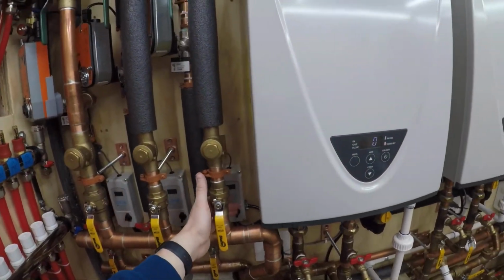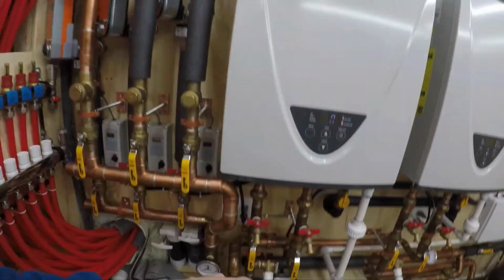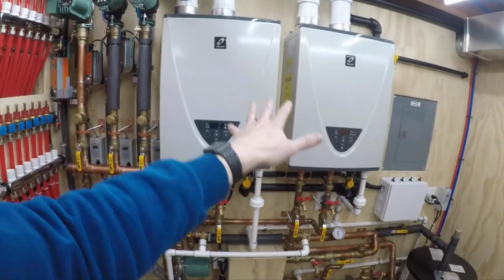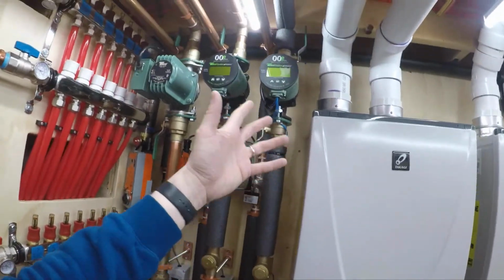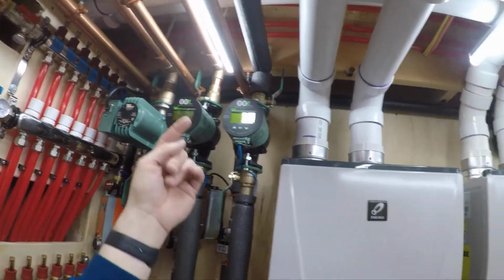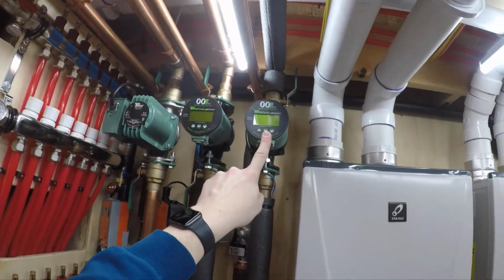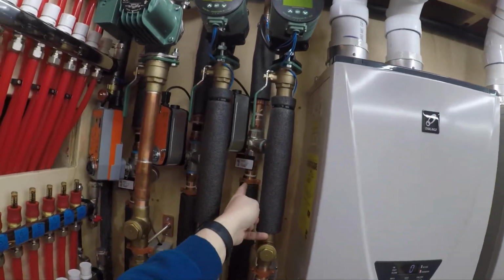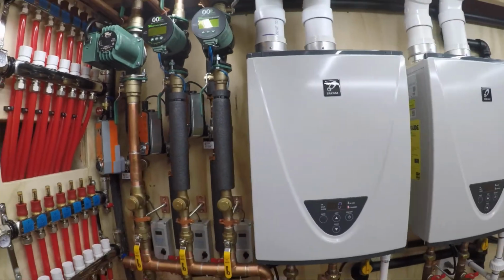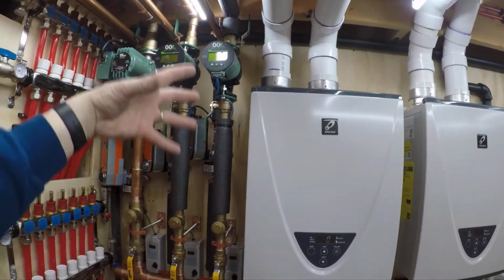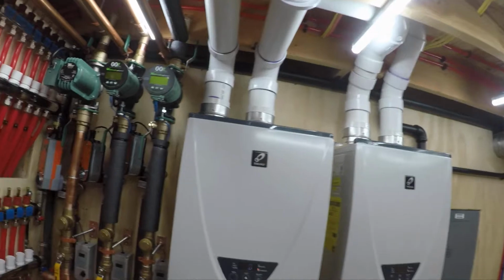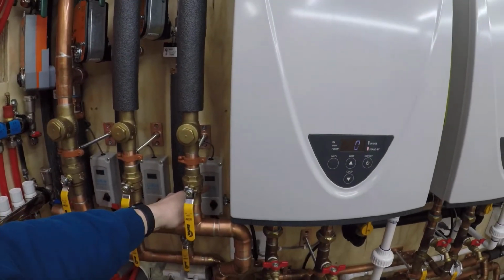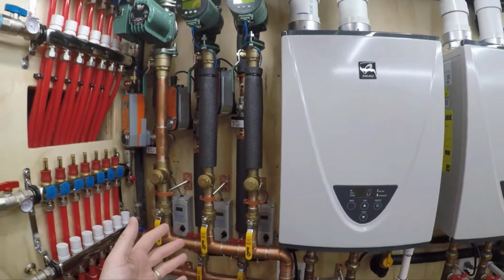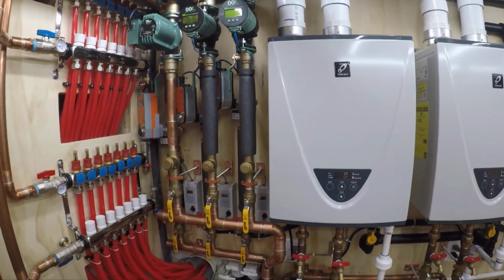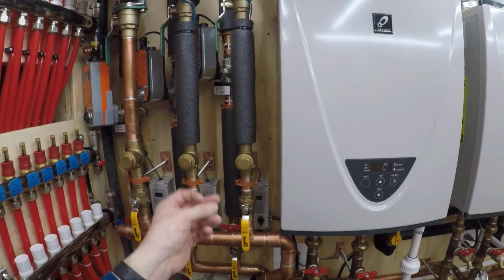the aquastat kicks on, it opens up this valve, it turns on the primary loop pump, the heaters come on, it starts picking up heat. I now have 120, 130 degree glycol going out to the floors. This pump sees that the supply is 130, but the return is only 80, and says, oh, better get moving. The pump starts pumping faster and faster and faster, uses more energy, but it starts pushing this heat through the loops, through the house, until the return comes up to whatever set point I have all of this at. Okay, which here I believe it's 90. Once it hits 90 degrees, it says, oh, okay, I'm satisfied.